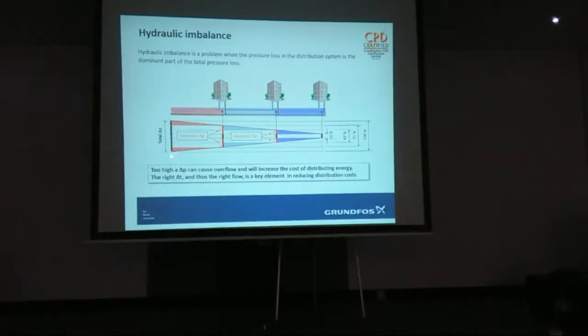You can have a smaller pressure pump doing all of the flow here, another pump here doing the pressure for this section but the flow for the whole lot, and here, a pump for that section only, so that would do that bit there. So the pressures would come down. So you're not getting imbalance within the circuit, particularly if certain blocks close down. That pressure wants to try to go somewhere else.